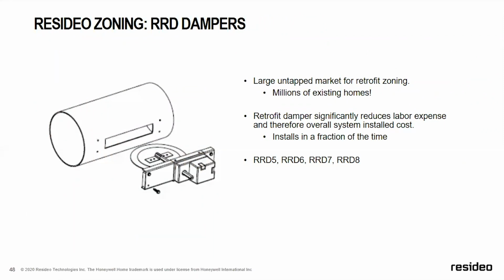RRDs, I love RRD dampers. We actually ship them with a decal that you peel and stick. You take a drill, open a little hole, cut a 1-inch slot, 10 inches long, stick this in. We ship it with the screws, 4 screws, wire it, and you're done. Fraction of the time, you don't have to take the ductwork apart. This again is for branch ducts, and I assume if you're doing high efficiency or high velocity, I've actually zoned Unico systems with RRD 8s. This damper works really well with that.